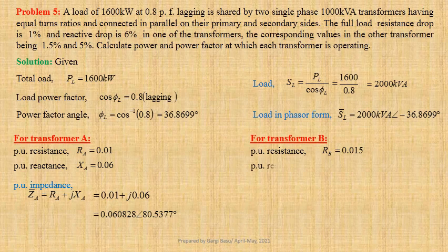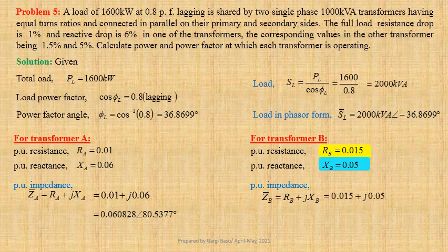For transformer B, given per unit resistance RB equals 0.015, per unit reactance XB equals 0.05, the per unit impedance of transformer B, ZB equals RB plus jXB, that is equal to 0.015 plus j0.05. This may be written in polar form as 0.052202 at an angle 73.3008 degrees.